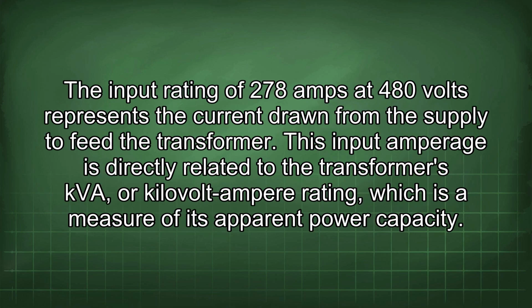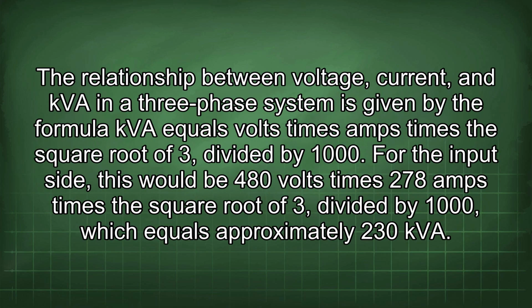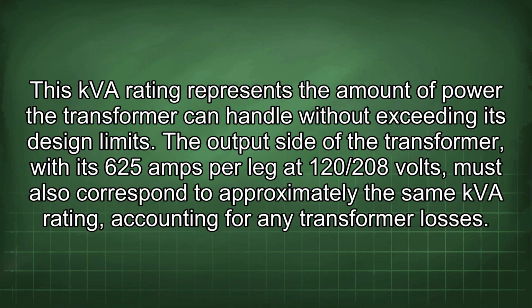The input rating of 278 amps at 480 volts represents the current drawn from the supply to feed the transformer. This input amperage is directly related to the transformer's kVA, or kilovolt ampere rating, which is a measure of its apparent power capacity. The relationship between voltage, current, and kVA in a three-phase system is given by the formula kVA equals volts times amps times the square root of 3 divided by 1000. For the input side, this would be 480 volts times 278 amps times the square root of 3 divided by 1000, which equals approximately 230 kVA. This kVA rating represents the amount of power the transformer can handle without exceeding its design limits.